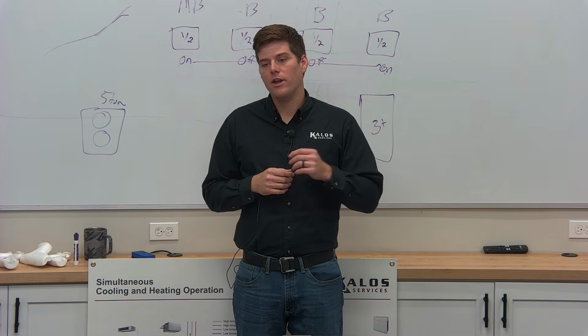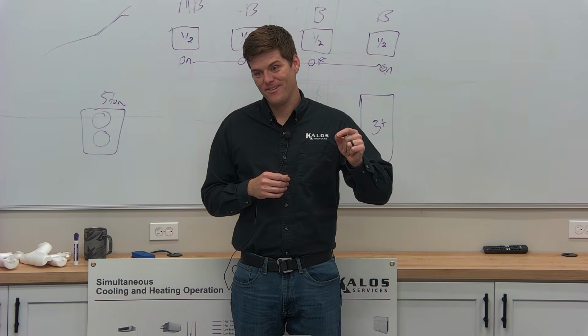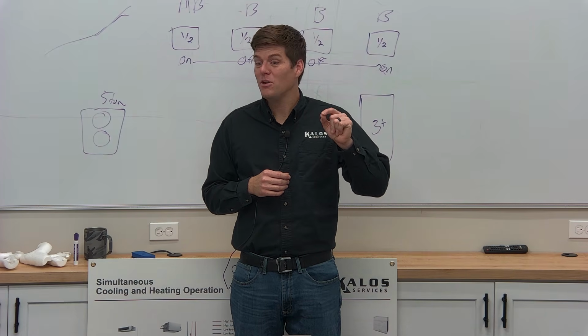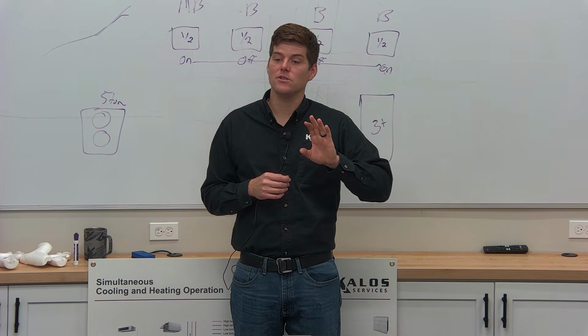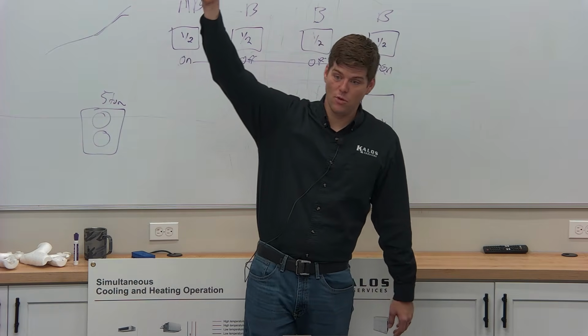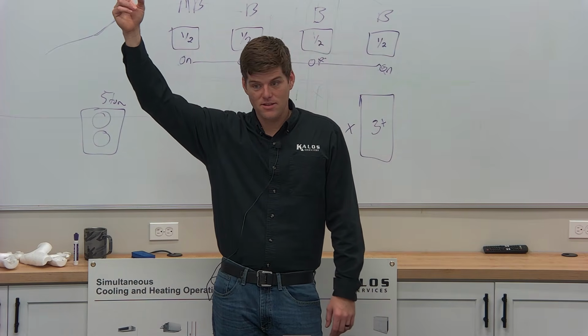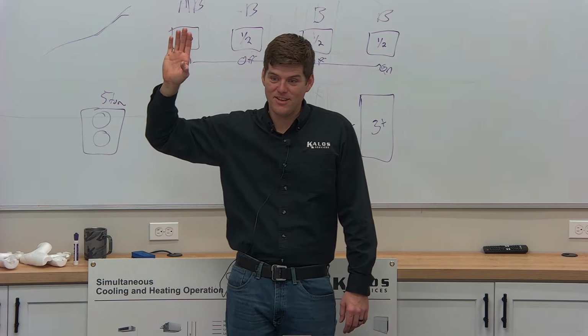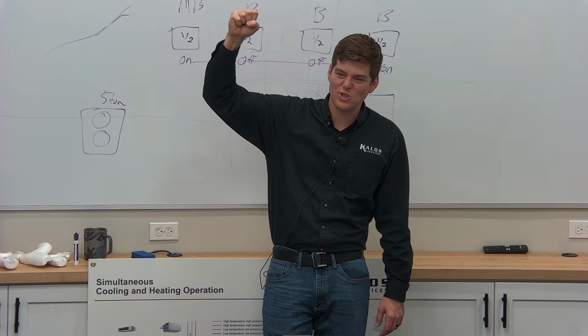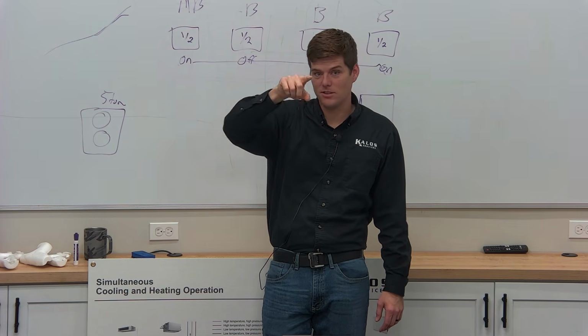You'll find incorrect flares will drip oil. They'll leak a little bit of refrigerant, not enough to damage capacity, but you'll see it. Ceiling tile, oil stain. Gives it away every time. You go to grab that line, and it just oozes oil. That's because the flare is too short.